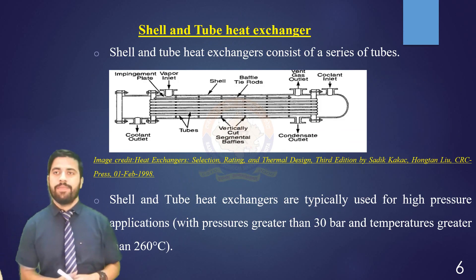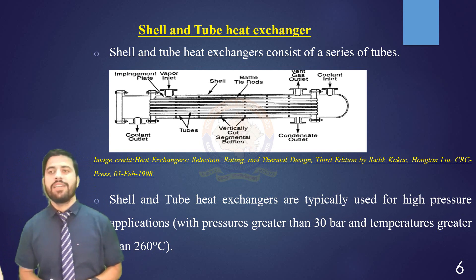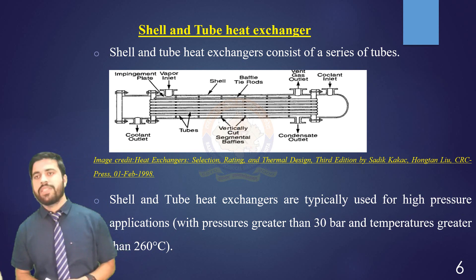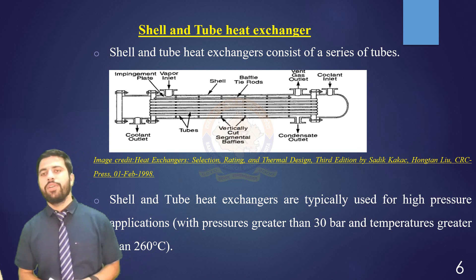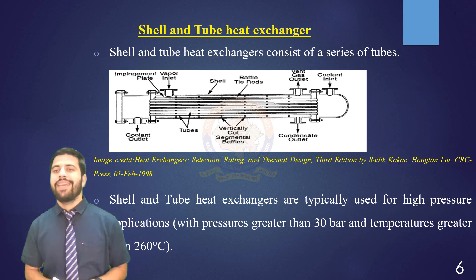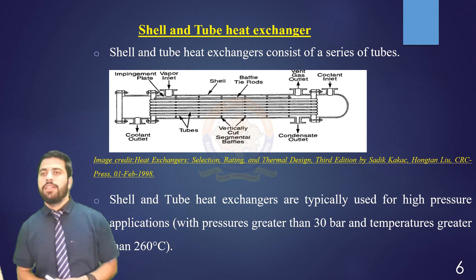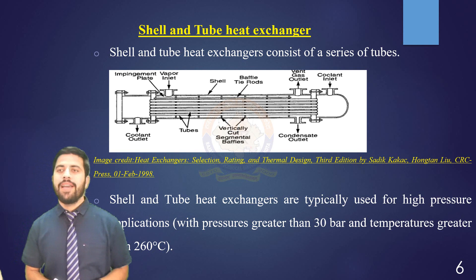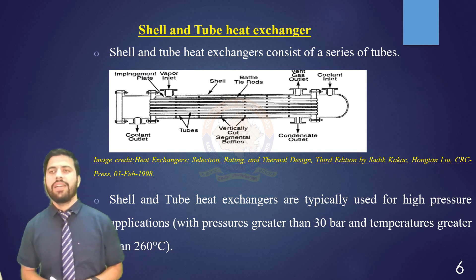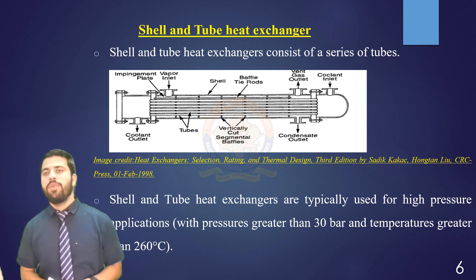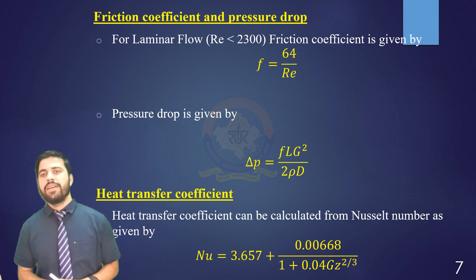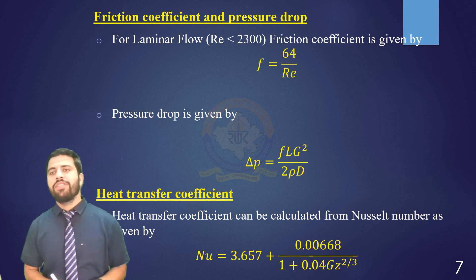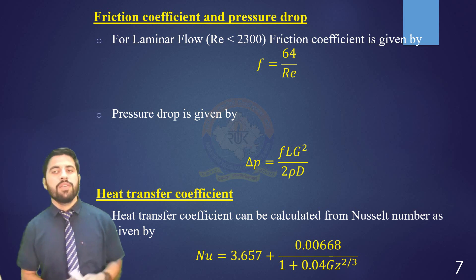The next type is the shell and tube heat exchanger. Shell and tube heat exchangers consist of a series of tubes. One set of these tubes contains the fluid that must be either heated or cooled. The second fluid runs over the tubes to either provide or absorb the required heat. Shell and tube heat exchangers are typically used for high pressure applications, with pressures greater than 30 bar and temperatures greater than 260 degrees Celsius, because they are robust due to their shape. In these heat exchangers, performance parameters like friction coefficient, pressure drop, and heat transfer coefficients can be calculated using the following equations.